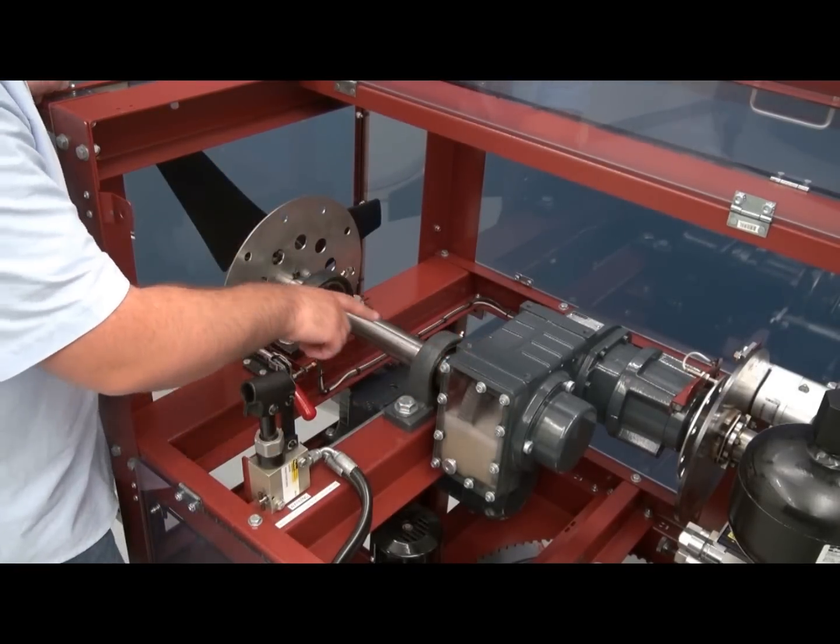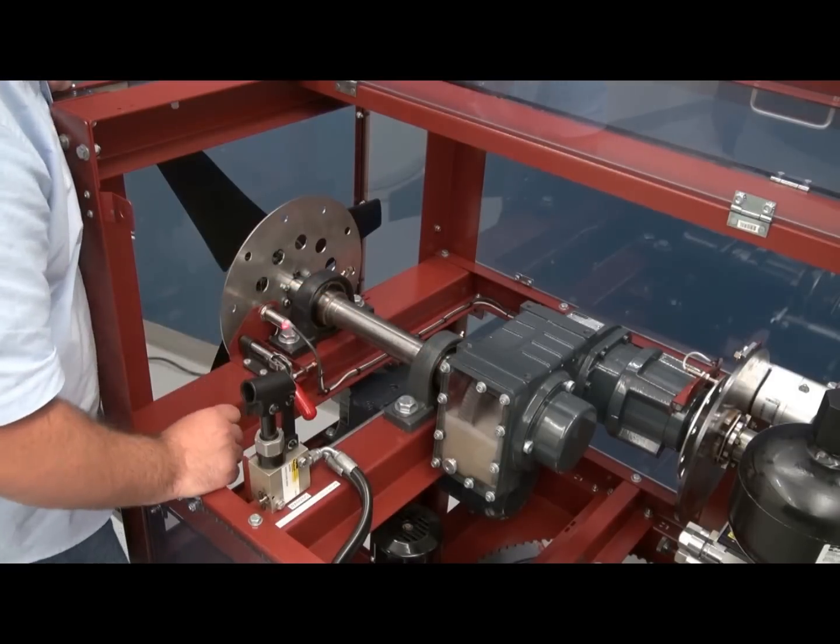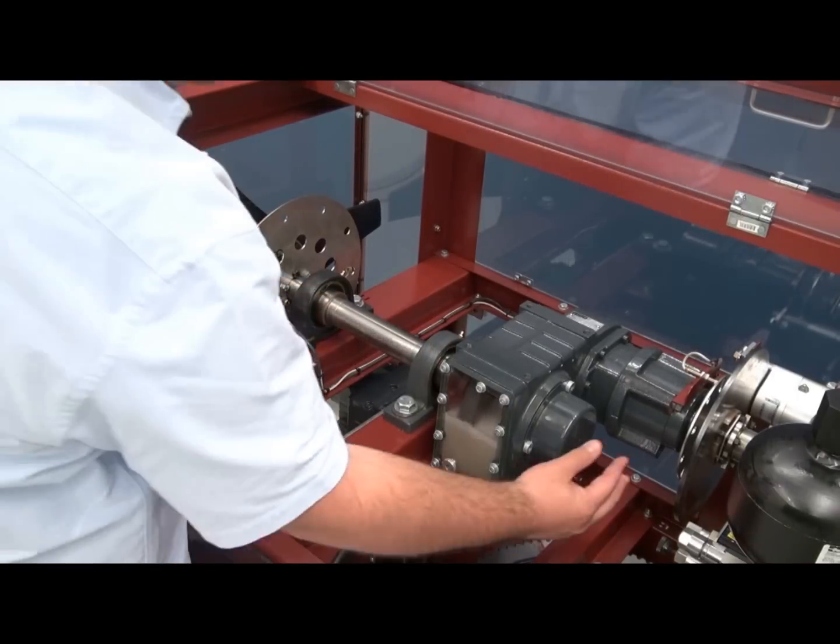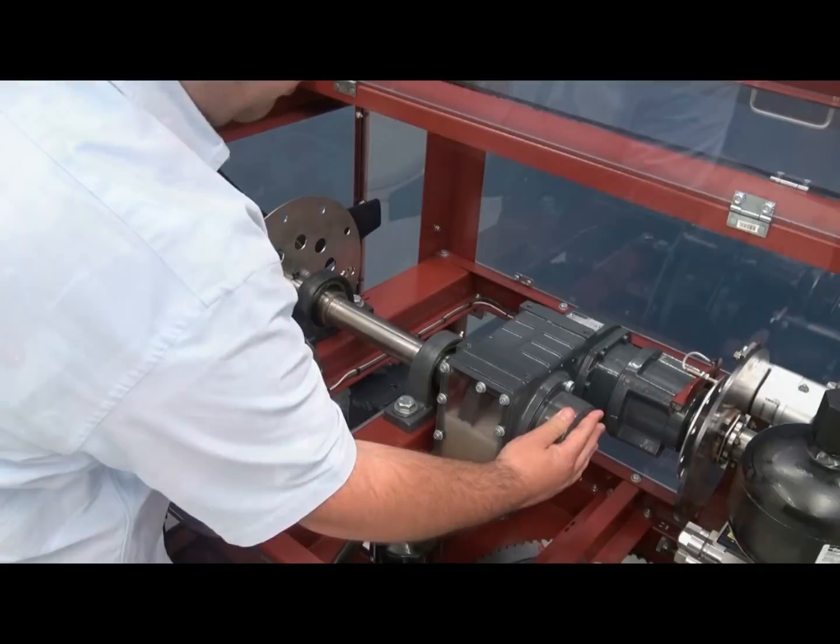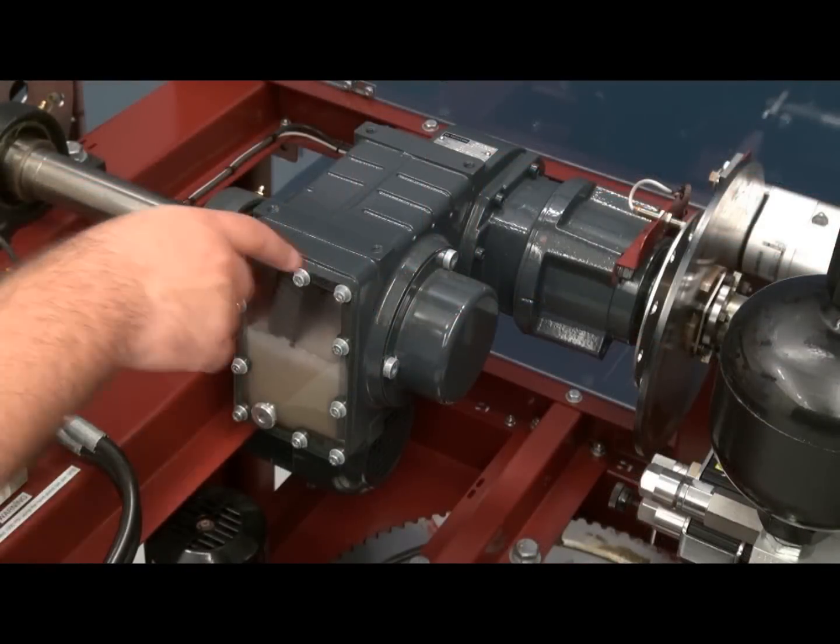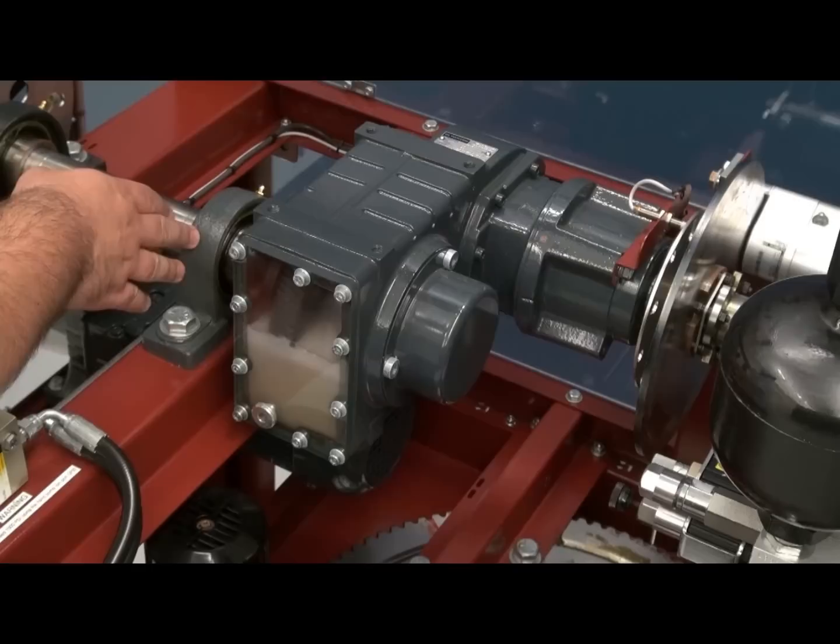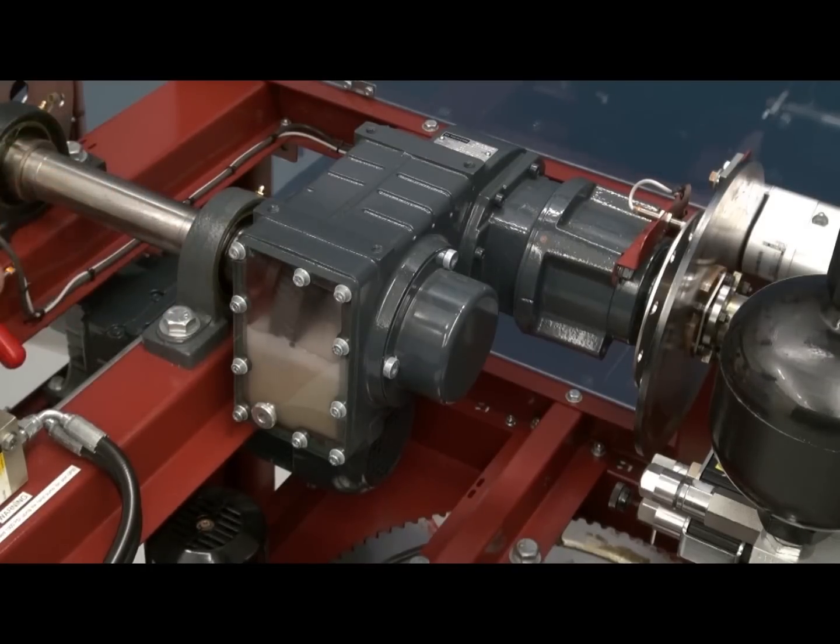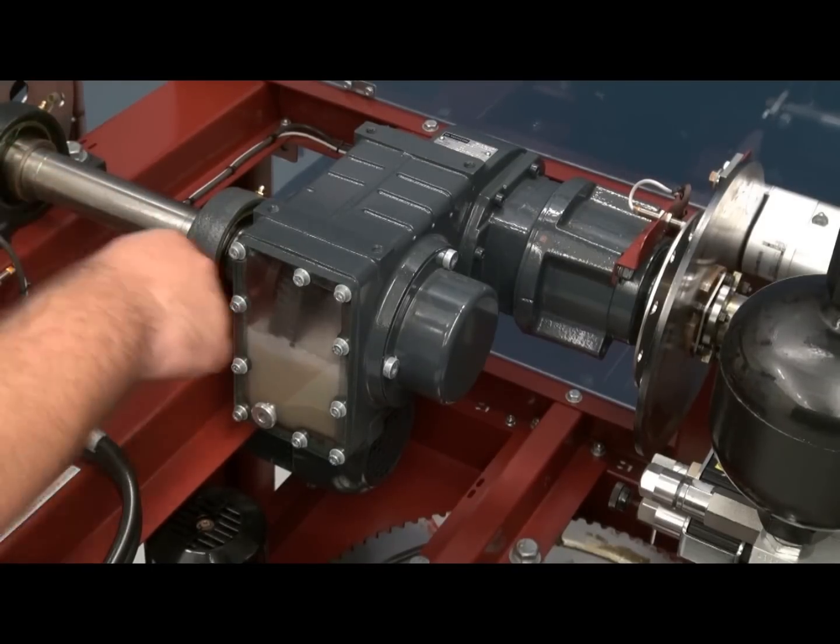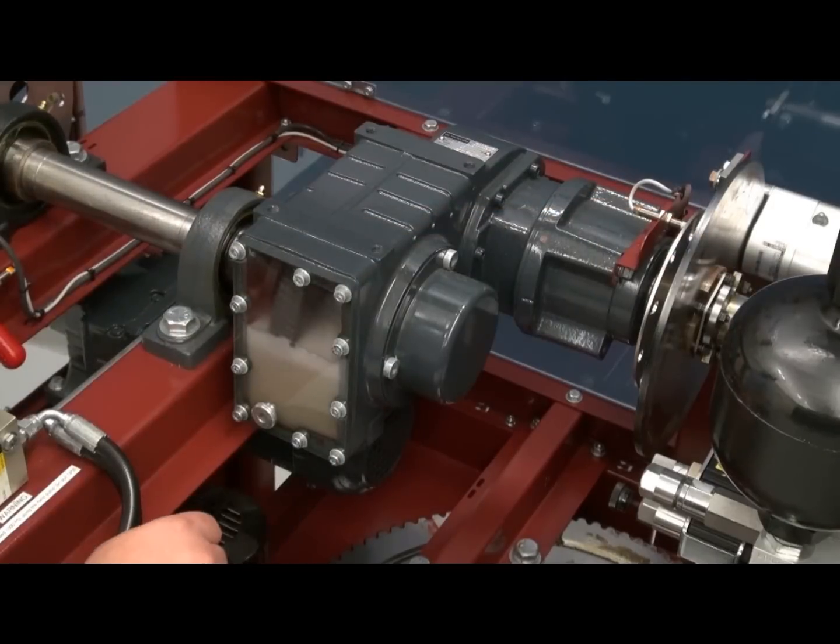The main shaft is directly fitted in the gearbox to a coupling system which is located here. The main part of the nacelle, which is also the part that drives a lot of maintenance tasks, is the gearbox. The gearbox will increase the speed of the low speed side to the high speed side for about 40 times, so you have at the rotor main shaft a speed of 47 rpm, and exit to the nominal speed of the generator, which is around 1800 rpm.